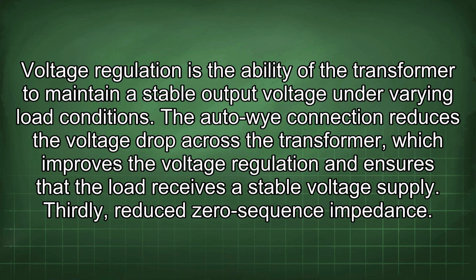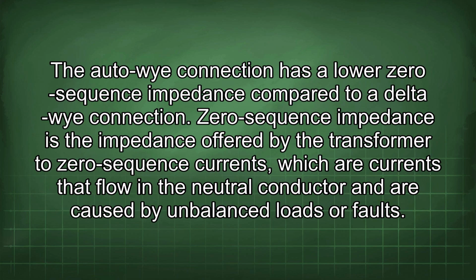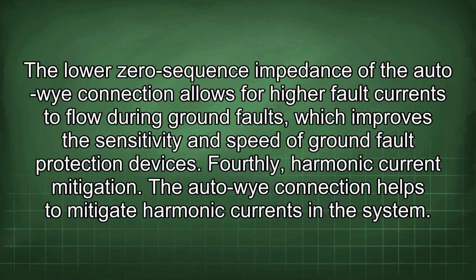Thirdly, reduced zero-sequence impedance. The Auto-Wye connection has a low zero-sequence impedance compared to a Delta-Wye connection. Zero-sequence impedance is the impedance offered by the transformer to zero-sequence currents, which are currents that flow in the neutral conductor and are caused by unbalanced loads or faults. The low zero-sequence impedance of the Auto-Wye connection allows for higher fault currents to flow during ground faults, which improves the sensitivity and speed of ground fault protection devices.